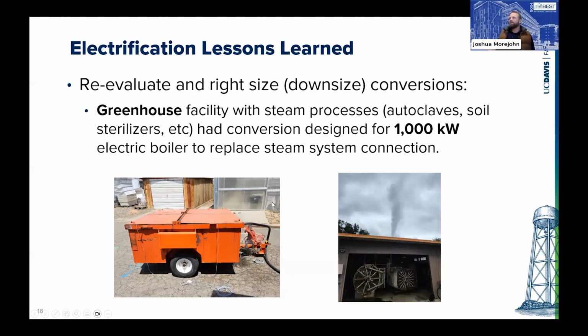So they can kill microbes and things before they do their growing. The consultant was going to replace it basically in kind with an electric boiler to provide steam. Once we're eliminating the steam system, the hot water wouldn't do the sterilization. So they were going to put in a 1,000 kilowatt electric boiler, but working in more detail with this site, they have some autoclaves over here as well for sterilization.